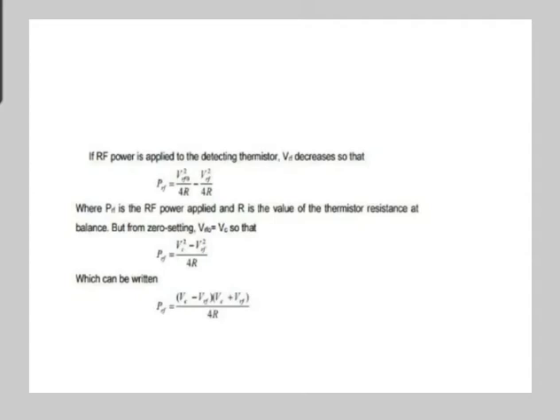The microwave power is then given to the thermistor R4, which is mounted in a coaxial line or a waveguide. Due to the heating of the thermistor, there is a decrease in the resistance and the bridge is unbalanced in proportion to the power given. So the meter, which is directly calibrated in milliwatts, shows this unbalanced current, and this method is hardly used in commercial microwave power meters because the thermistor is more sensitive to changes in air temperature.